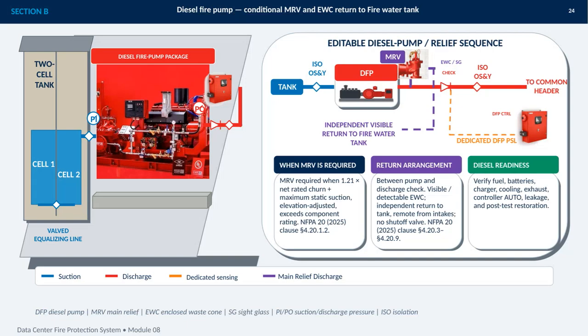This slide shows the diesel fire pump arrangement and the conditions governing its relief and return piping. At the center is the diesel fire pump package, with suction from the two-cell firewater tank through the valved equalizing line, and discharge through the isolation valve and check valve to the common header. Pressure indication is provided on the suction and discharge sides, with dedicated sensing for the diesel pump controller. The main relief valve, or MRV, is conditional. It is required when 1.21 times the pump's net rated churn pressure, plus the maximum static suction pressure adjusted for elevation, exceeds the rating of a system component.